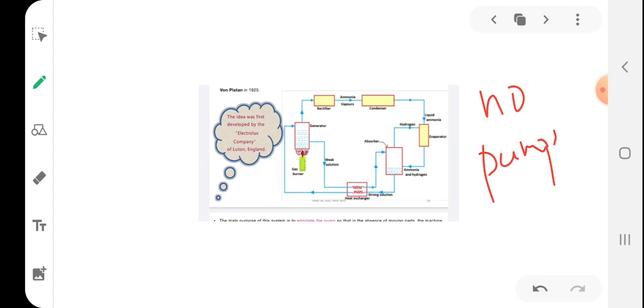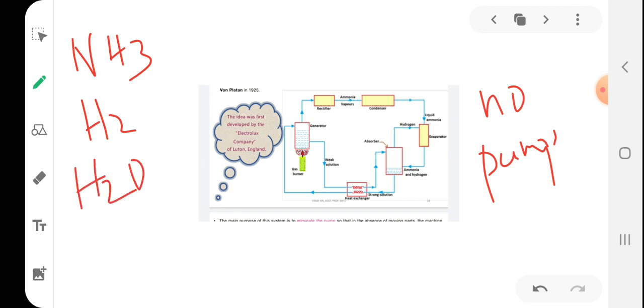There are three fluids used in the system. What are the three fluids? First one is ammonia, then hydrogen gas, and water. Ammonia is the real refrigerant, the core fluid. Ammonia being a toxic refrigerant, but due to the absence of moving parts, there is very little chance of leakage, because there is no compressor or pump. Whenever there is a moving part, the chances of leakage are higher. So even though ammonia is toxic, you don't have to worry about its toxicity, and the food stored in the refrigerator space will not be affected by the refrigerant. That is the advantage of this system.